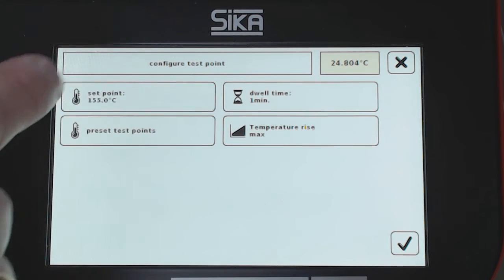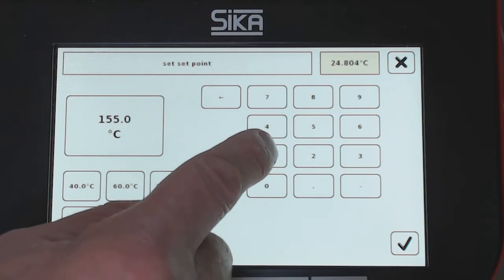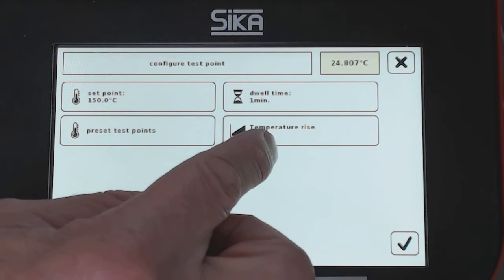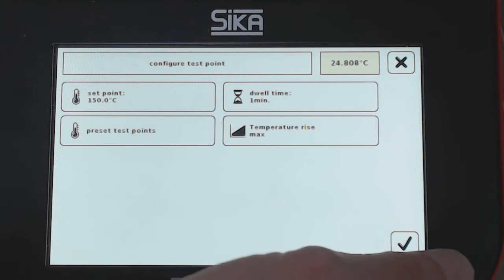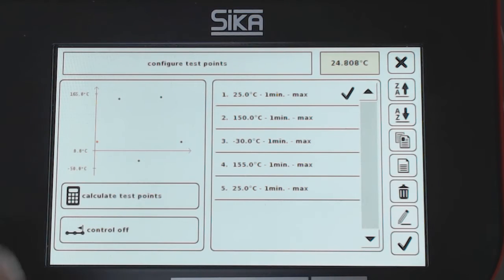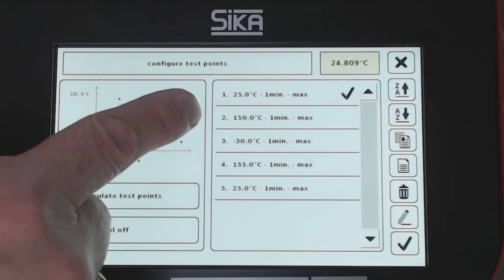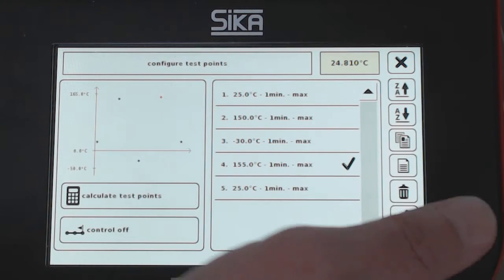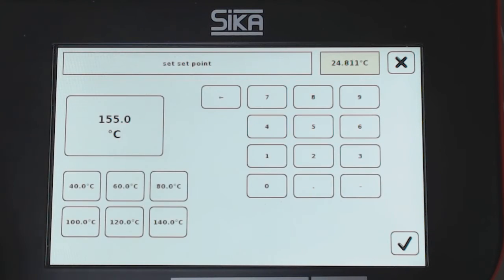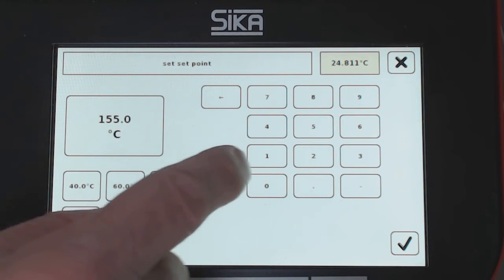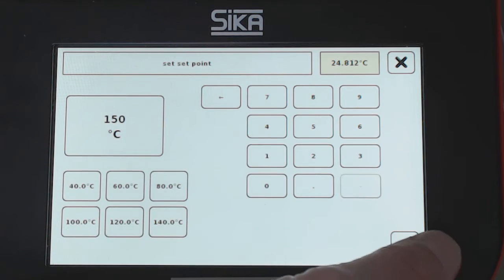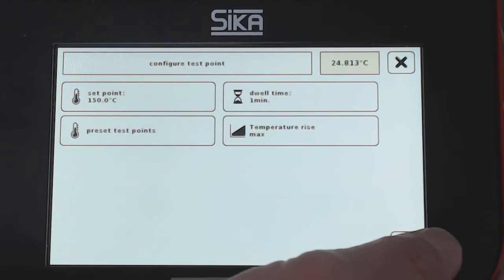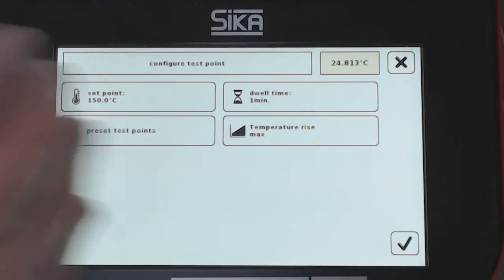Dwell time: 1 minute. I go to 150 and confirm. Temperature rise is at maximum speed. I confirm. This is the first point. For the next point, I have to edit again from 155 to 150. Confirm. Maximum speed, dwell time, 1 minute. Confirm.